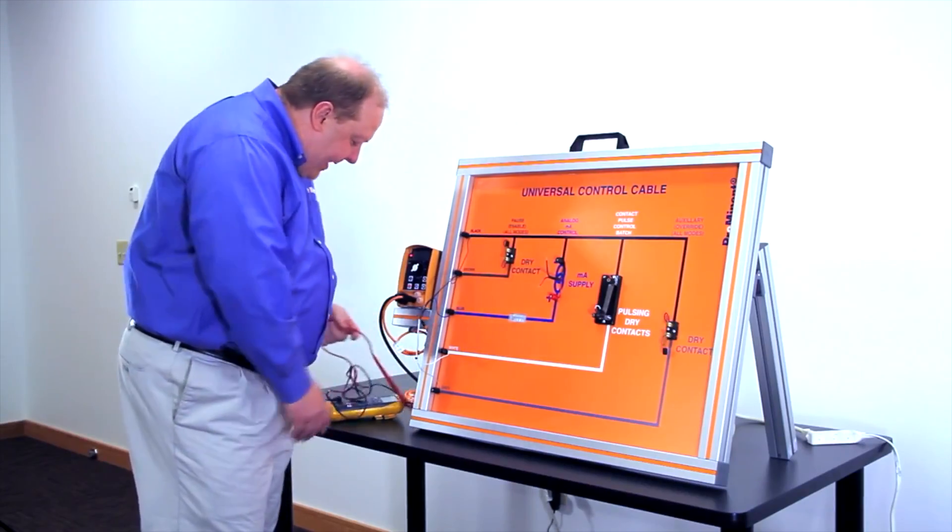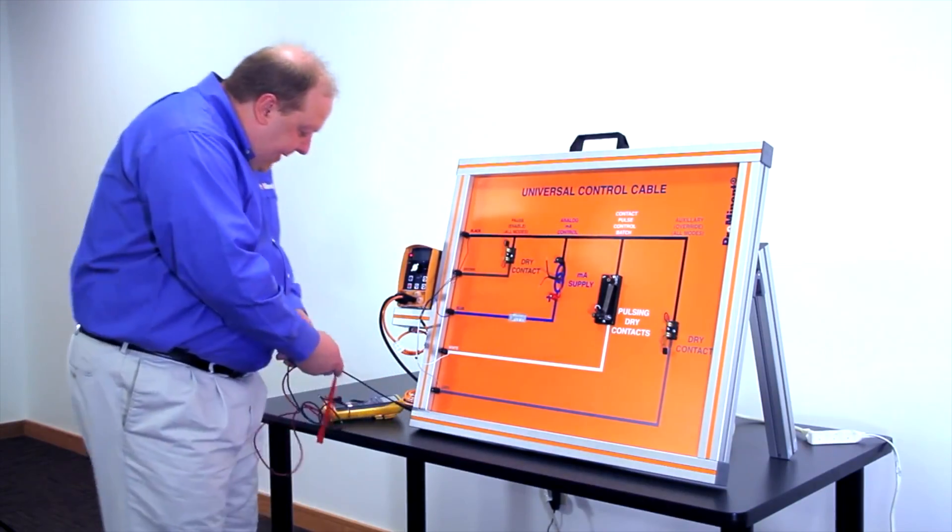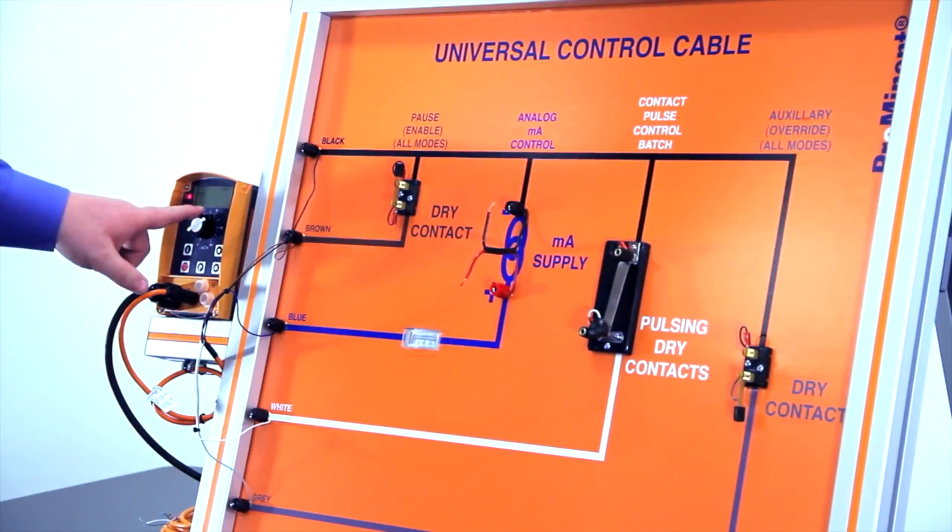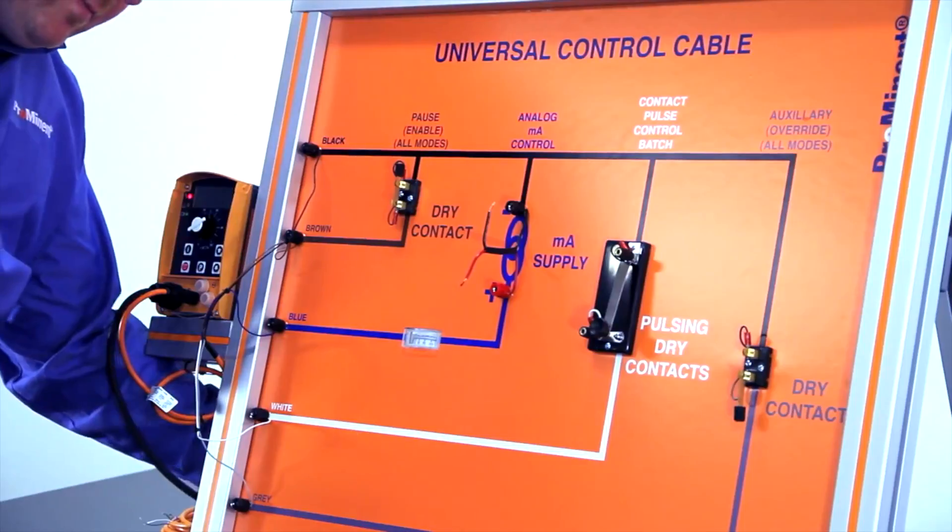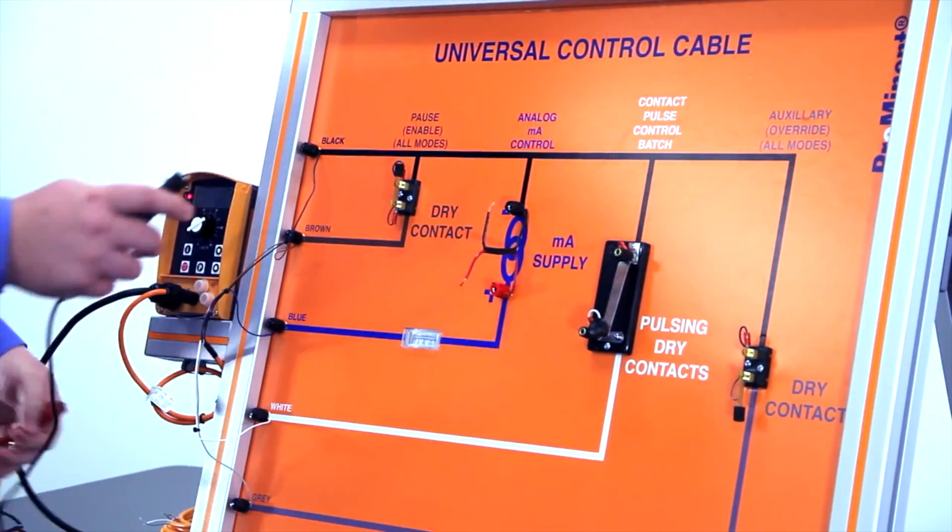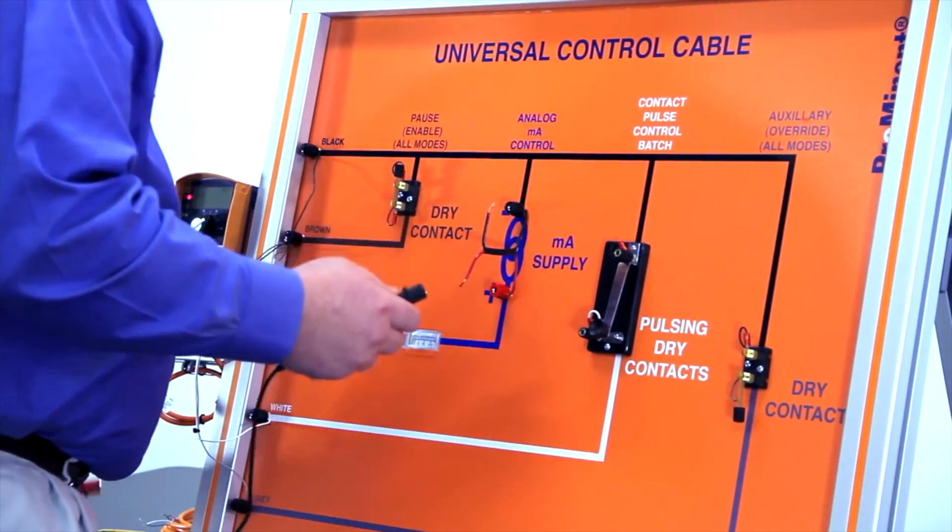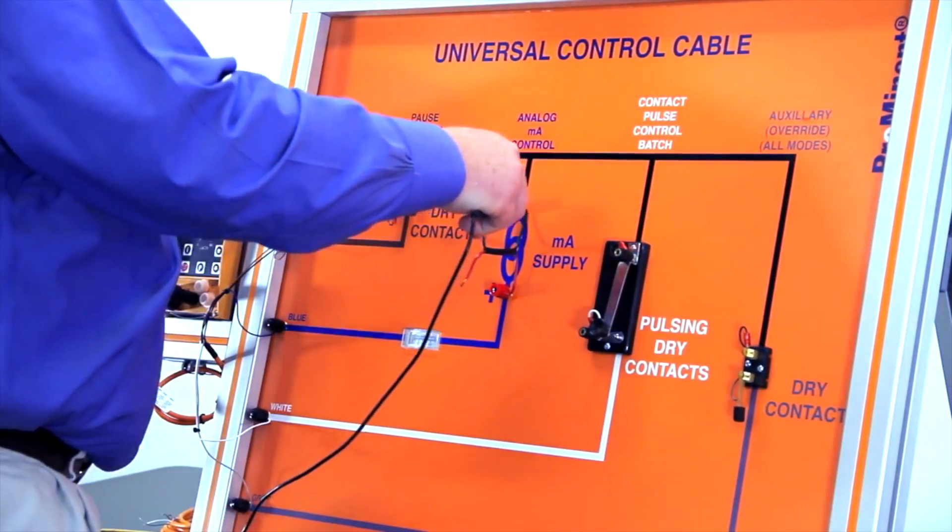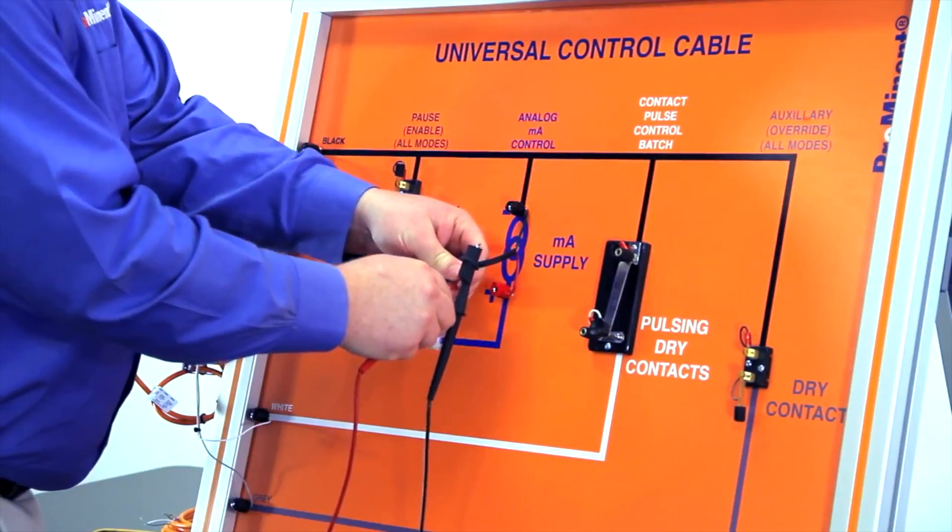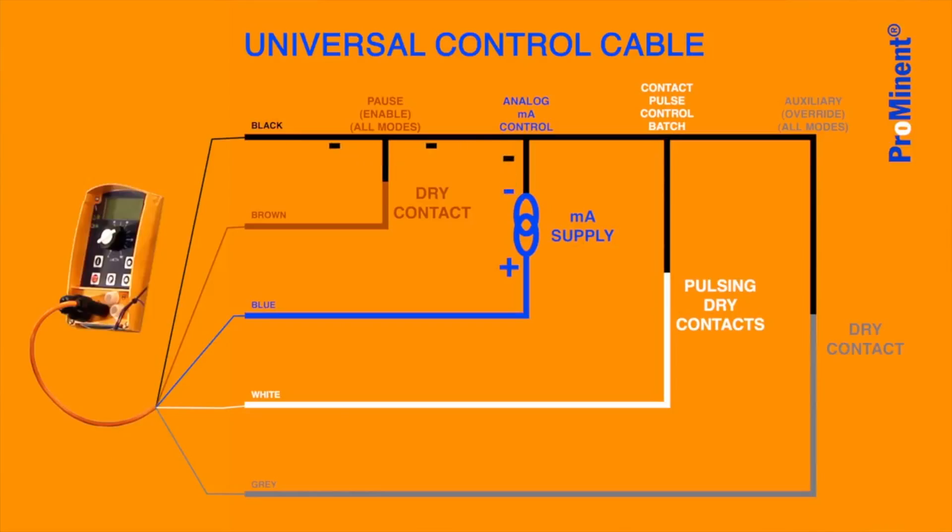Then we have to put an analog signal, typically 4 to 20 milliamps, into our pump. We have to put that input signal into our universal control cable. We'll connect the negative of that signal to the black wire, which again is made to the brown wire with a dry contact. The positive of that signal goes to the blue wire back to the pump.